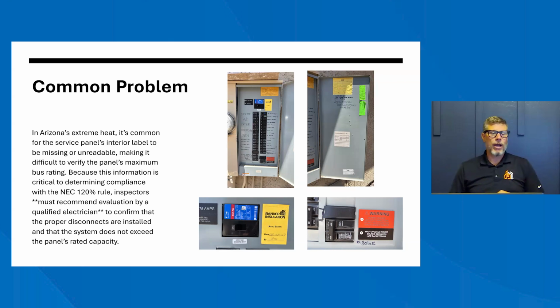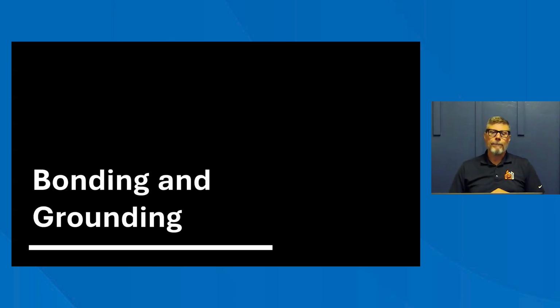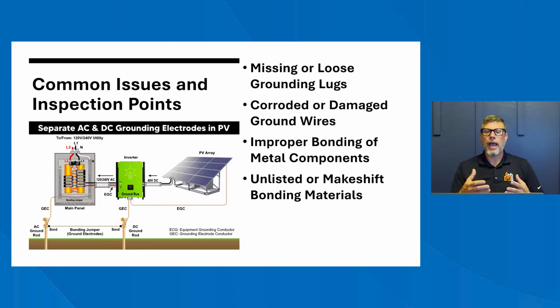So with that, let's talk about bonding and grounding. I'm not going to beat you guys up with bonding and grounding, but let's talk about it briefly. You don't have to be a code expert when it comes to grounding, but you do need to recognize some things that just don't look right. Some of the common things that you'll see are missing or loose grounding lugs. Sometimes you'll just see the wire wrapped around the gas pipe or the water pipe. There's no lug; it's just wrapped there. If it's loose or missing, you want to call that out.